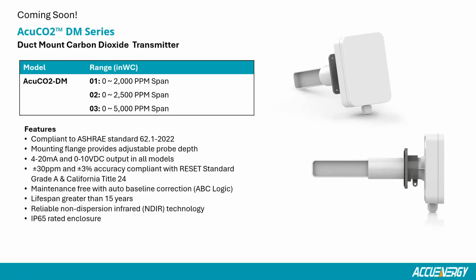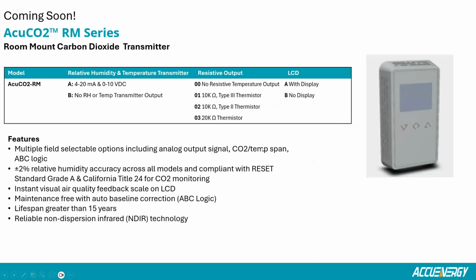Also, the auto baseline correction, or the ABC logic as it's branded, is utilized to provide basically maintenance free operation, with no need to calibrate under normal circumstances. Typically, we've seen sensors with this similar technology last up to 15 plus years under normal operating conditions. If it does, for whatever reason, need to be calibrated, we do have that capability. But right now, everything on the duct mount sensor is going to have the ABC logic applied to it. And then an IP65 rated enclosure. And again, it's going to have that same label that shows you how to wire it and everything like that.